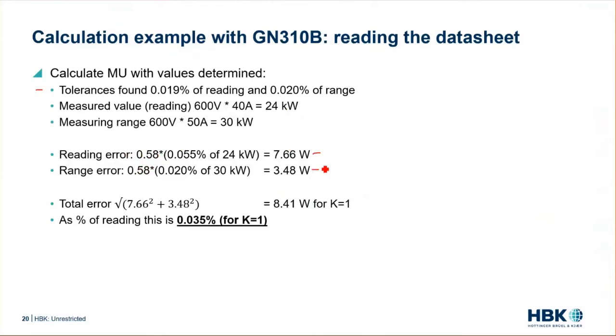We calculate the individual errors in watts, then use geometric addition — squaring both values, summing them, and taking the square root. The measurement uncertainty at this specific measurement point is 8.41 watts for k equals 1, which as a percentage of reading is 0.035 percent. K equals 1 indicates a one-sigma coverage of the result.